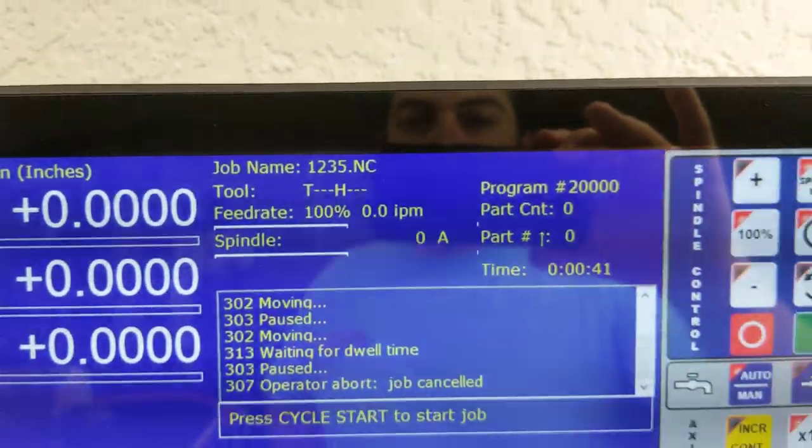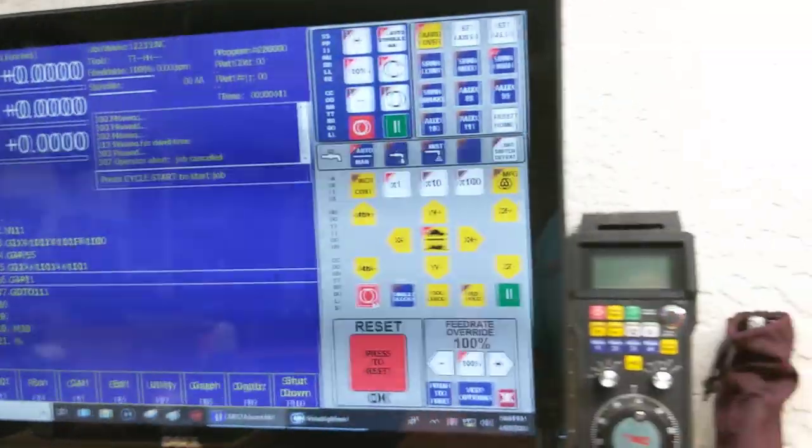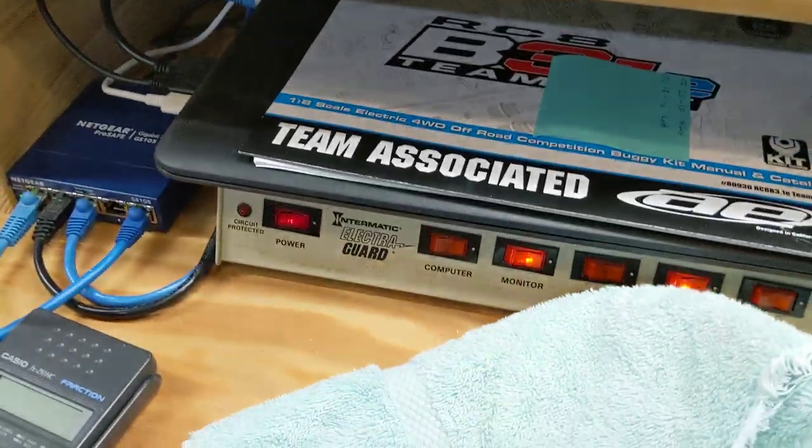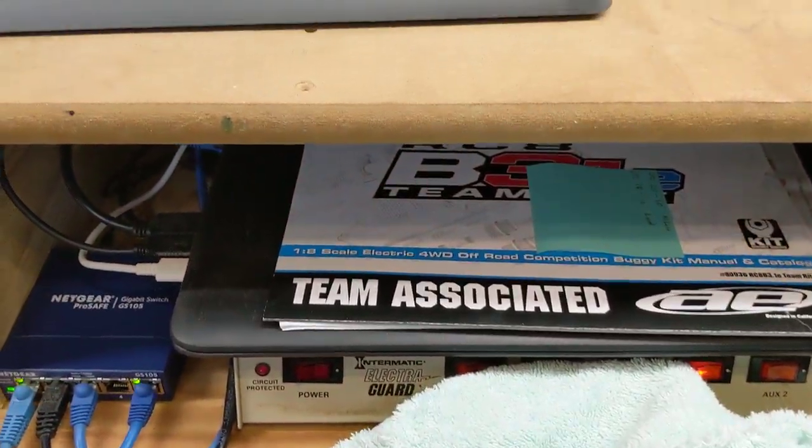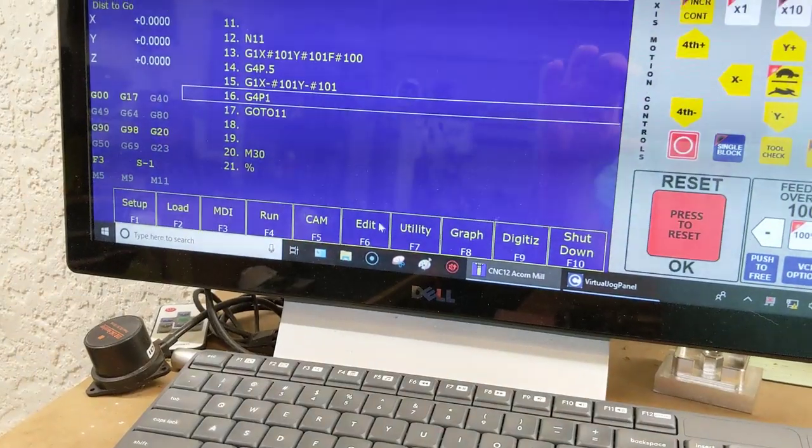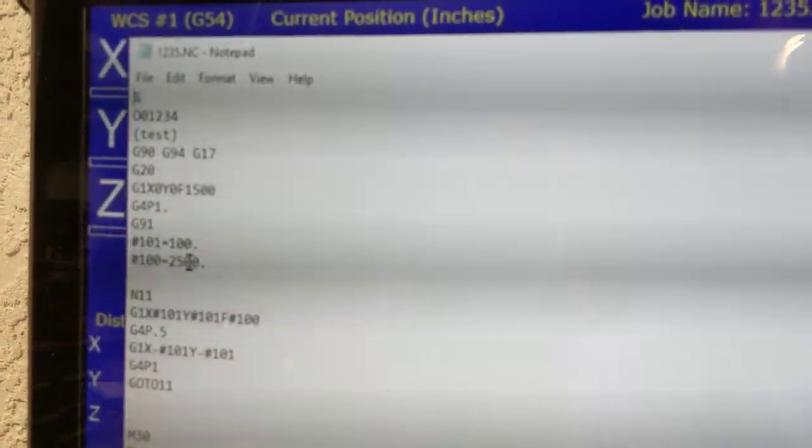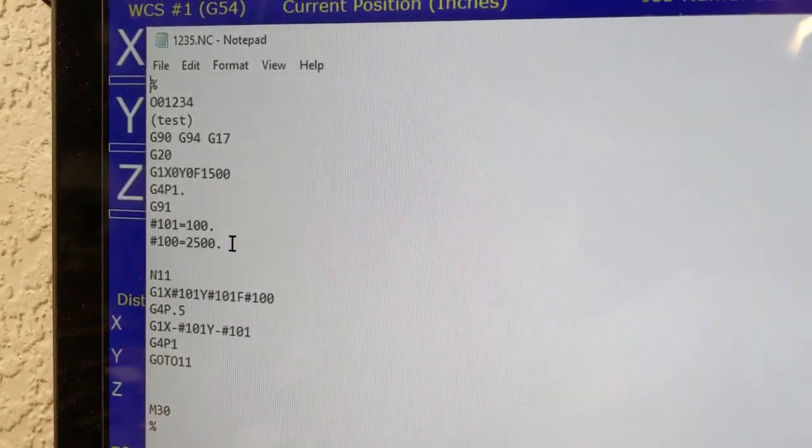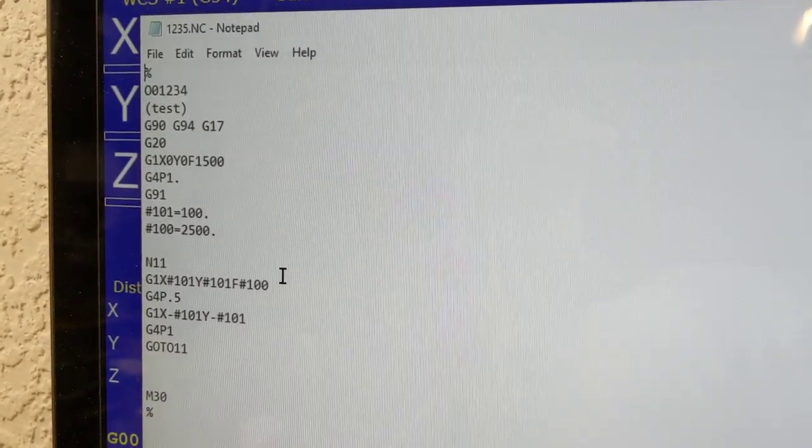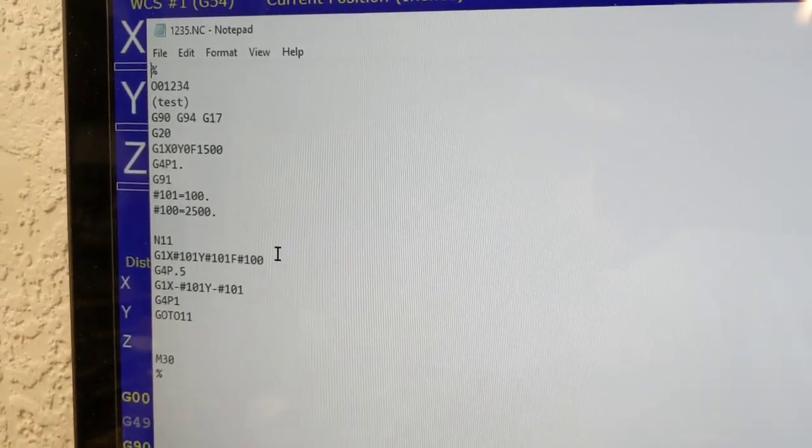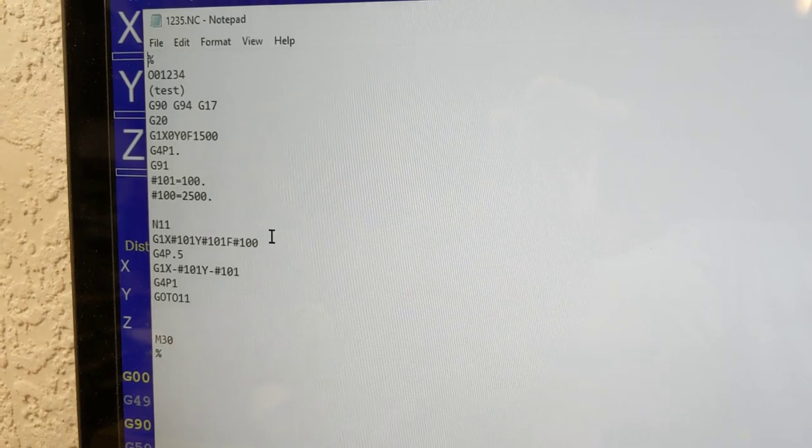So let's fire this thing up and let's see what happens. So what I've done, trying to do this one-handed, it's not easy but I'll do the best I can. I have a program here and I'll tell you in advance, well let me just show it to you. It's easier to show it to you. I have written a little program, it's a macro program. Basically what I'm going to do is run this motor 2500 RPM. I'm going to go 100 inches in one direction and I'm going to come back 100 inches, and what I want to see is that the motor stops and starts in the exact same place.